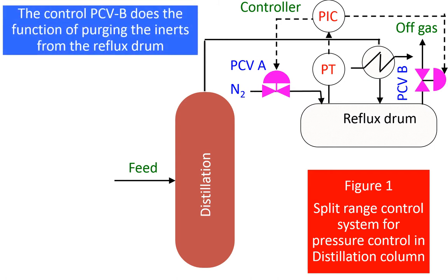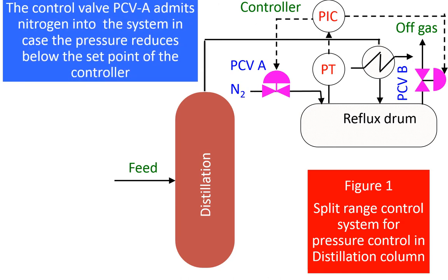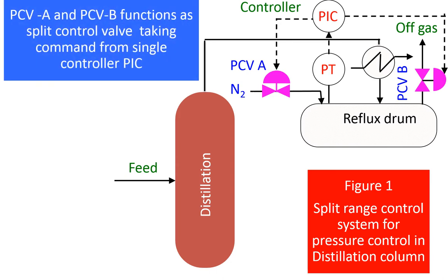Instead, the split range control method is used. There are two pressure control valves. One is a nitrogen valve, PCVA, that outputs nitrogen into the reflux drum. And another pressure control valve, PCVB, that lets the non-condensables go to the atmosphere by purging.